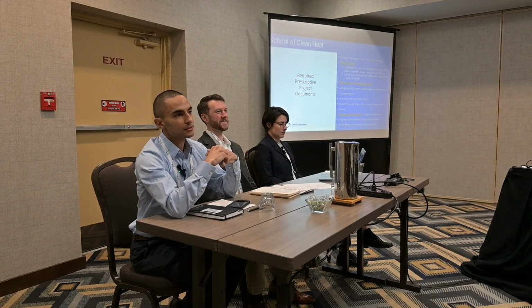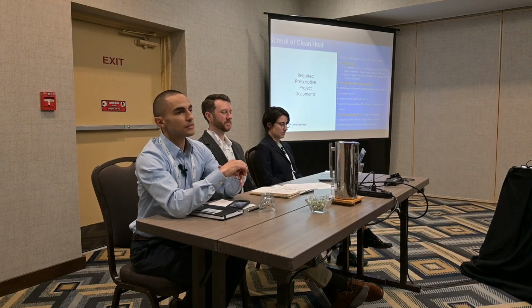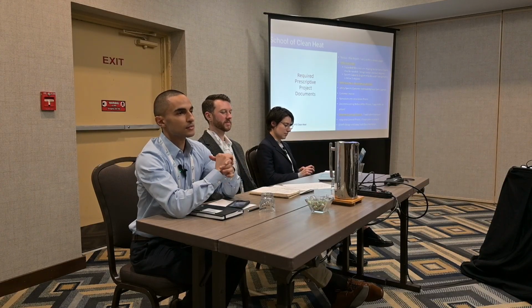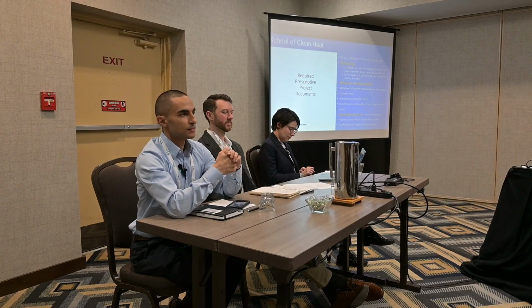So typically a block load, room by room, your main load is going to come out similar. But for design purposes, a lot of times you need to do that room by room to get what the required CFM per room is. But in terms of meeting the program eligibility, as long as you do a block load and show that the installed heat pump meets 100 to 120% of the load, you'll be eligible for the program.